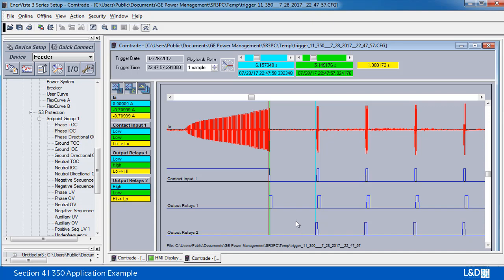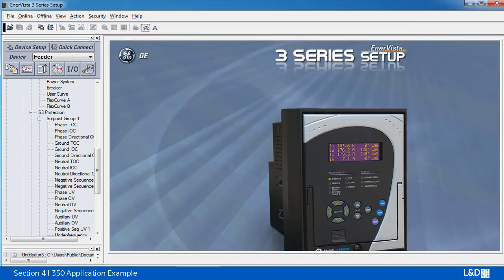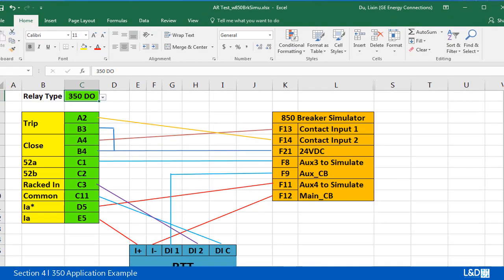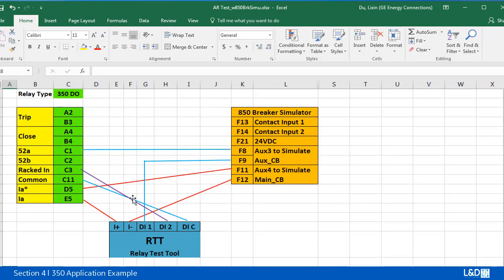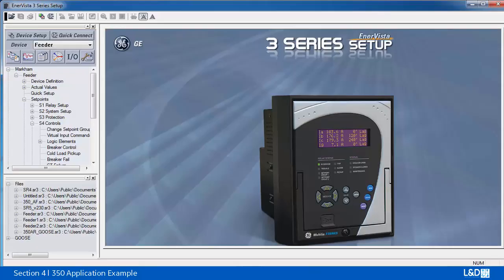And that's the first part of this auto reclose testing by using the hardwired. And now I will introduce the second part of the test by using the goose message. Instead of using the hardwired, now this wiring from the 350 to 850 contact inputs will be replaced by the goose message. In the 3 series configuration, we're going to set 4 remote outputs. We're going to do this by using the advanced goose.